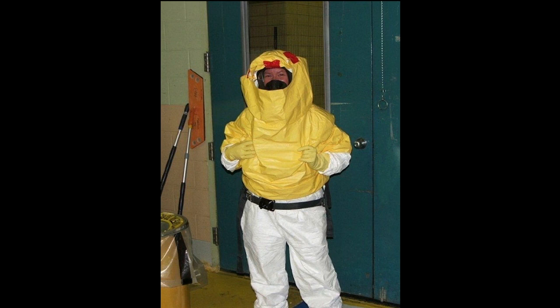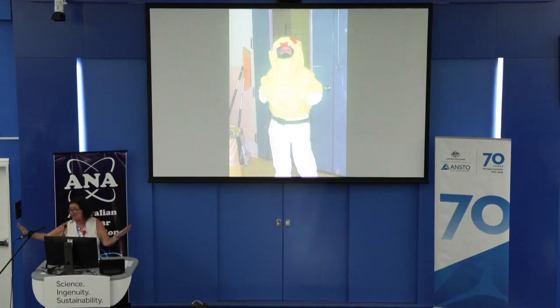What we do is pressurize containment. Containment normally works at a vacuum, like your vacuum cleaner, just a little below atmospheric pressure, about 3.5 kPa. So we depressurize it, then pressurize it up to 70 kPa above atmosphere, and walk around with giant backpacks full of leak-detecting tech, spraying every crevice in the plant that has a containment opening, looking for leaks.